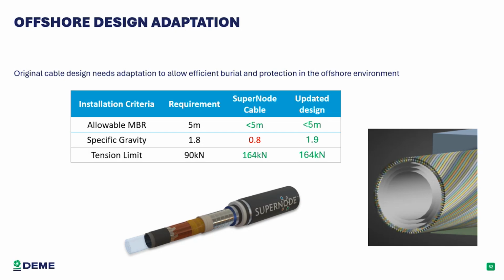As you can see in this table, MBR stands for minimum bending radius. The cable has sufficient bending radius, compatible with our requirements. Tension limit as well is compatible with our requirement. But its specific gravity, or density, in the original version — a typical design more for land installation — was not dense enough, not high enough, to be installed offshore according to our requirements. So together with Supernode, agreeing on different modifications, we proposed an improved design of the external layers of the cable, complementing the design to reach a specific gravity of 1.9.